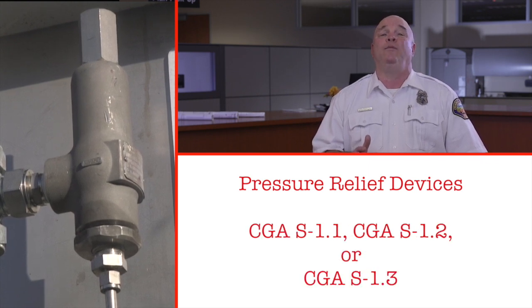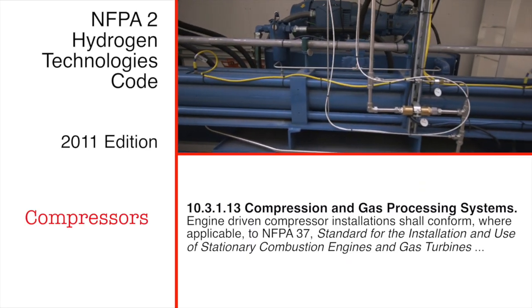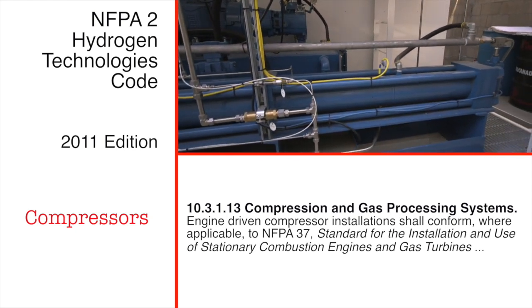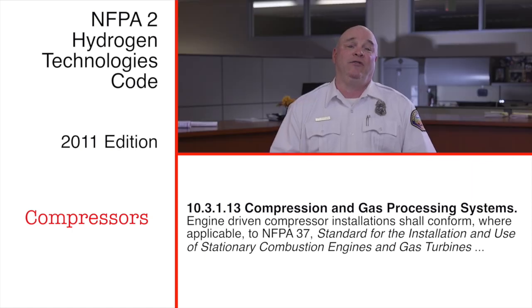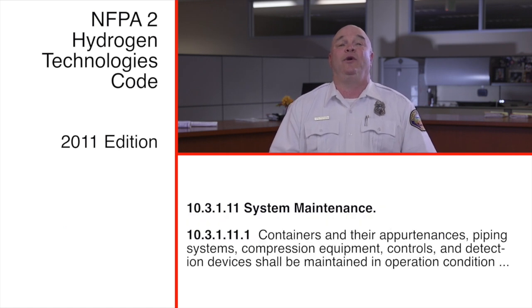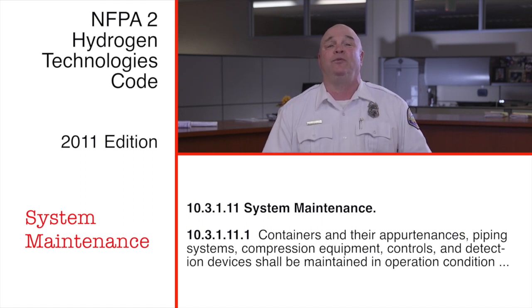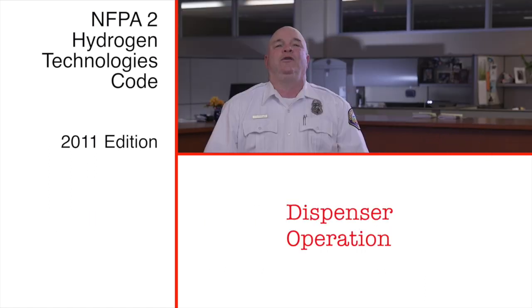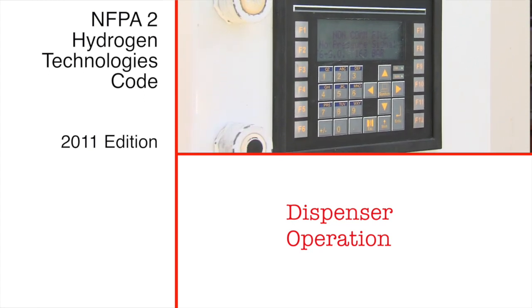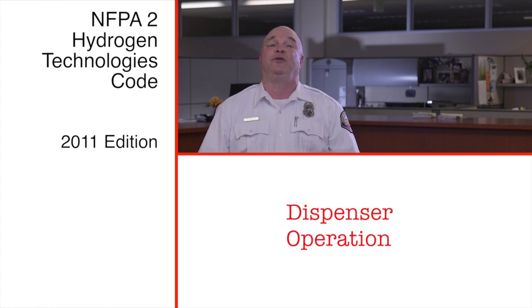The pressure relief devices should also meet CGA S-1.1, 1.2, or 1.3 depending on the storage design. Compressors are addressed in Section 10.3.1.13. Note that compressors should be designed to shutdown in the event of a power outage or when an emergency shutdown device is activated. Section 10.3.1.11 sets maintenance requirements. Hoses, nozzles, and breakaways must be examined monthly or according to the manufacturer's instructions. Controllers must verify system pressure integrity. Key requirements include automatic system shutdown when a complete fill is achieved. Vehicle fuel tanks shall not be subjected to 125 percent of their marked service pressure.